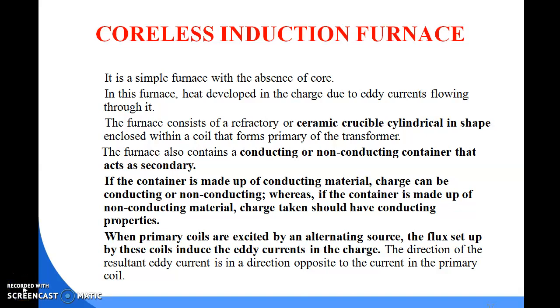So we discussed that coreless induction furnace. It is a simple furnace with the absence of core. In this furnace, heat is developed in the charge due to eddy current flowing through it. The furnace consists of a refractory or ceramic crucible cylindrical in shape, enclosed within a coil that forms a primary of the transformer.